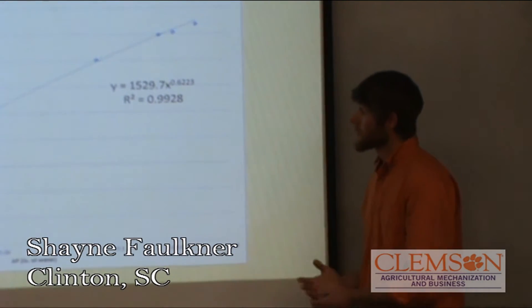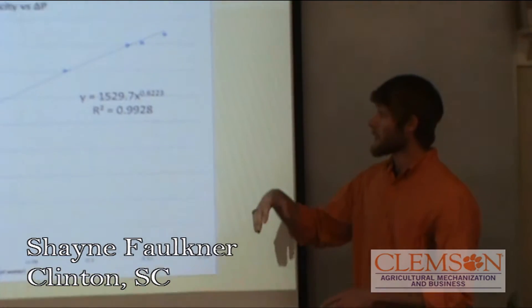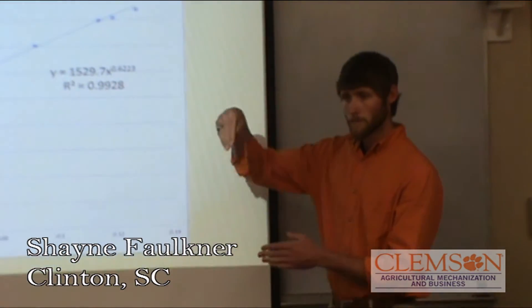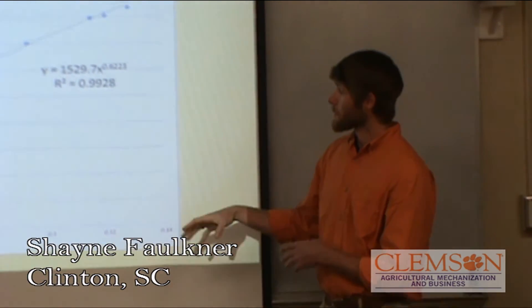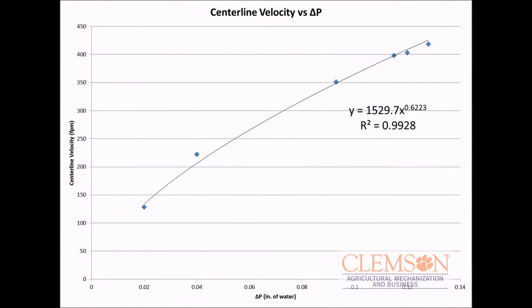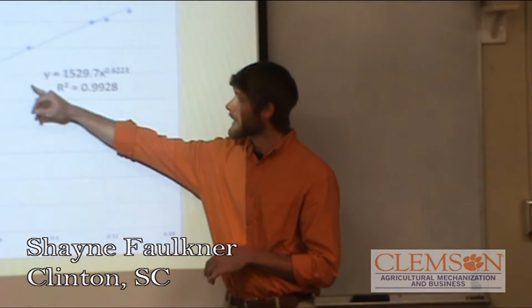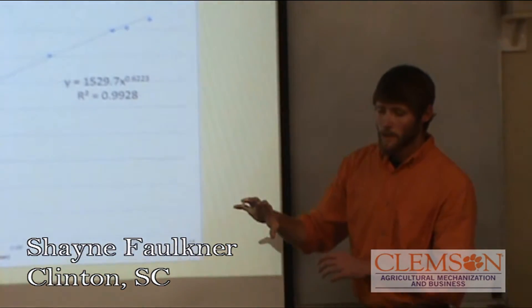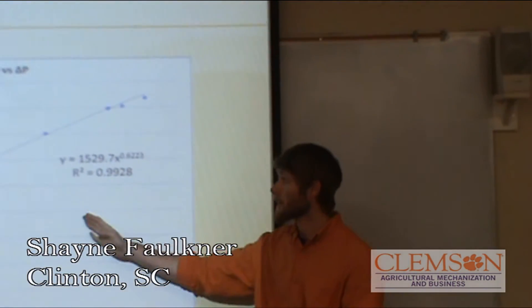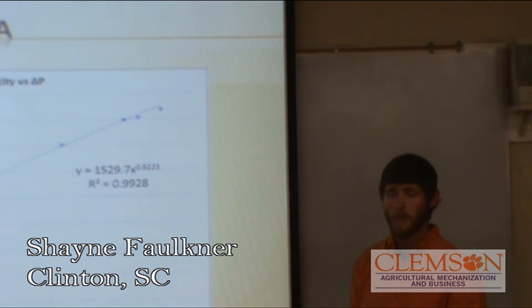This is our first testing stage. Those green stoppers you saw run along one side — there are three on the top and one in the center. We set our anemometer down to about 24 inches, about halfway in, so that we could start plotting different velocities based on what static pressure we were seeing. The first data point was from the four smallest 500 CFM fans. The next one was when we added the two 800 CFM fans in the middle. Then there's a big gap to the next point from struggling with the fan design and the shutter opening. We weren't able to get accurate readings until it was fully open and we were getting uniform air speed.